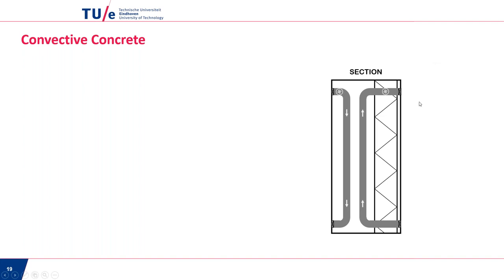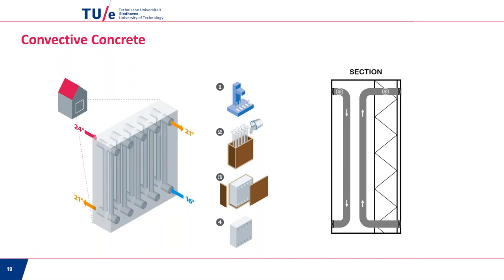If we start installing air conditioning to counterbalance overheating, we lose all the benefits of reduced heating demand from insulation. The idea here is to use a special way of 3D printing to create a building slab with ducts embedded. By activating fans during the night in summer, we can charge the thermal mass on the inside of the insulation layer with cool air from outside, then absorb more heat gains during daytime. This becomes a kind of heat exchanger — no air mixing involved — taking outside air to cool the thermal mass so it can absorb more during the next day.